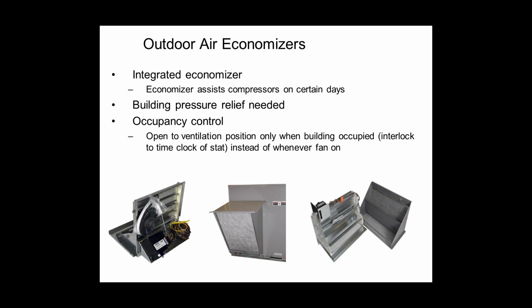The problem is that a normal packaged rooftop unit opens the economizer to its minimum position whenever the fan is on, because it doesn't know anything else. So that means if your rooftop unit turns on in the middle of the night for setback heating or cooling, which it's definitely going to do, and the fan turns on, which it's definitely going to do, you open up the ventilation damper and you suck in 20 or 30% outside air to ventilate a building that has no people and does not require any ventilation during that time period per code. Right? It's a huge, huge energy waster, and it's very easily preventable. Every single economizer controller put on every single rooftop, at least in the past 8 years, if not longer, has an input on it for occupancy.